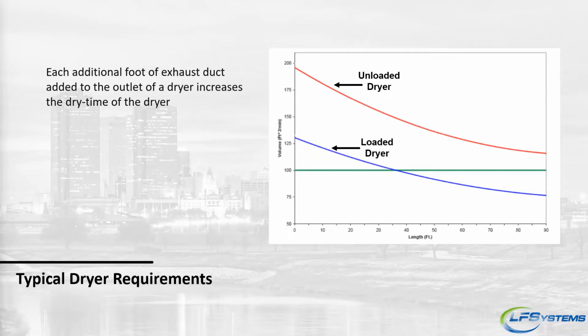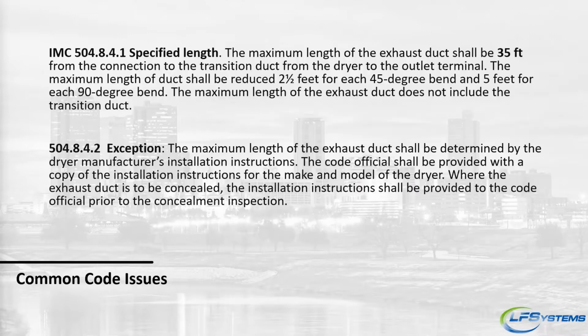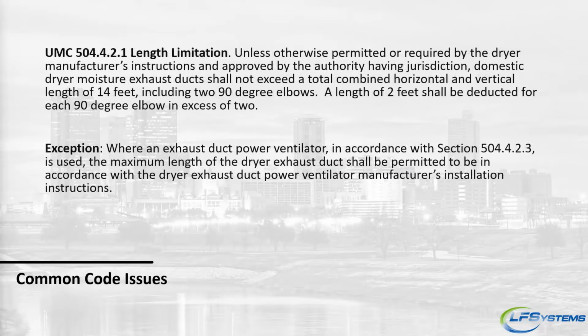That 35 feet, actually, reading into the code, again, 35 feet is in IMC 504. Deduct 5 feet for every bend. The exception being that a dryer manufacturer does give you the exception. And then same thing for UMC. These are just to kind of show you where in the code it is. So you're looking at 504.